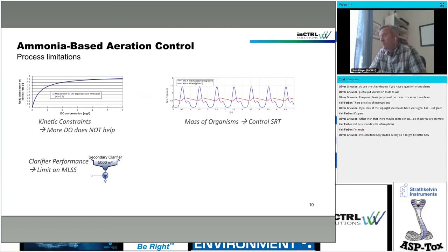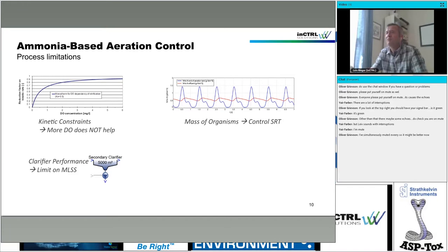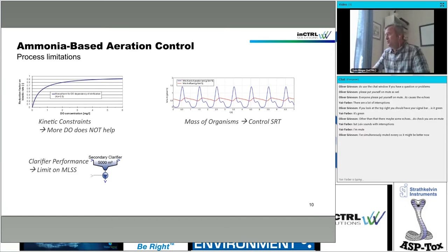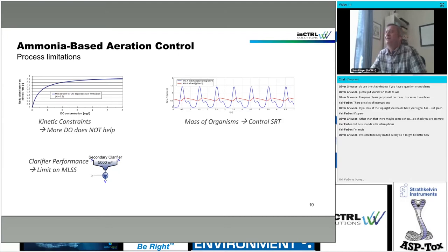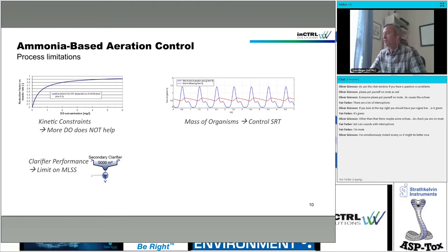Let's look at process limitations for ammonia-based aeration control specifically. Most of the control systems I saw failing — people didn't have a proper understanding of process and equipment constraints. The first one for ammonia control is a kinetic constraint: if you reach a DO of around 2 mg/L in all sections of the plant, not only where you measure DO, then more DO is not helping. Increasing aeration intensity, sending more air into the tank, will have no impact. Ammonia control is very powerful in the other direction — if you switch off the air completely, there is no nitrification left — however, if you increase aeration, there is a limit; it's saturating, and more air is not helping.